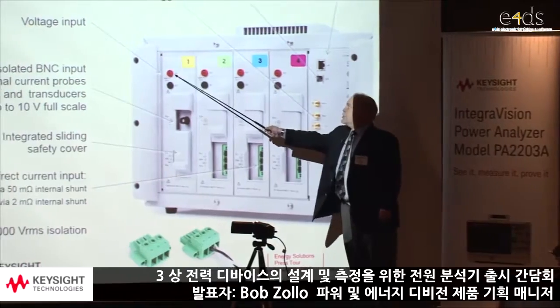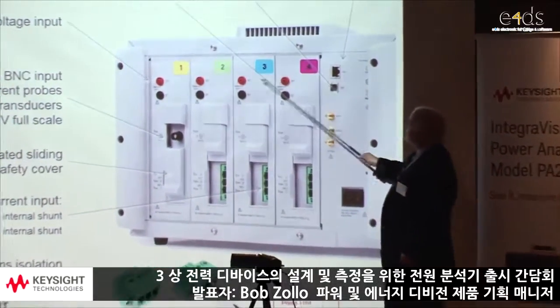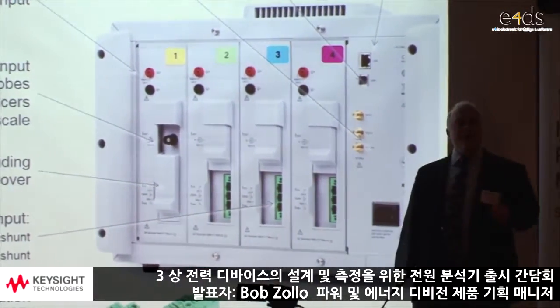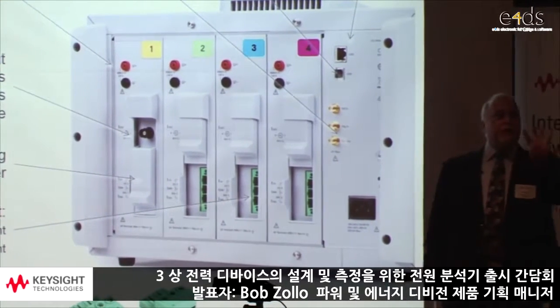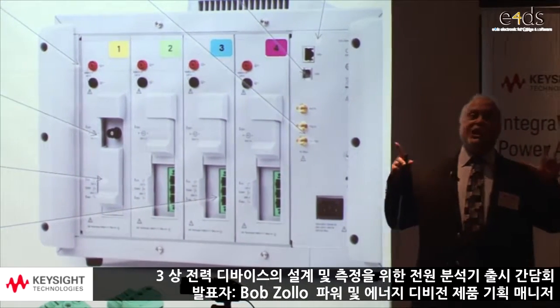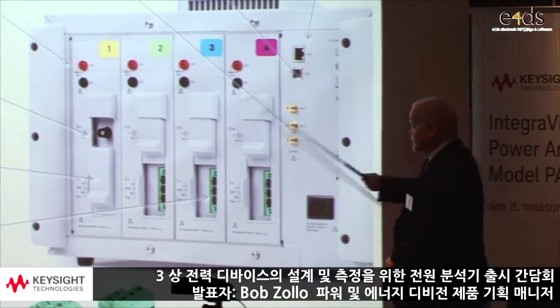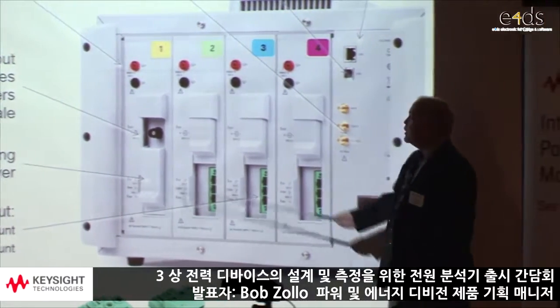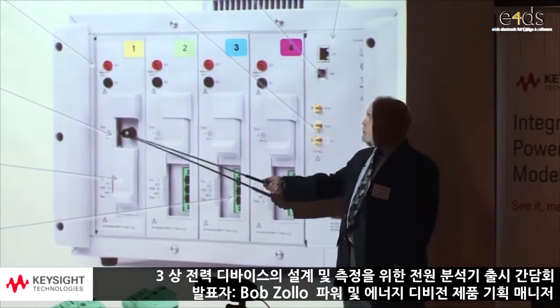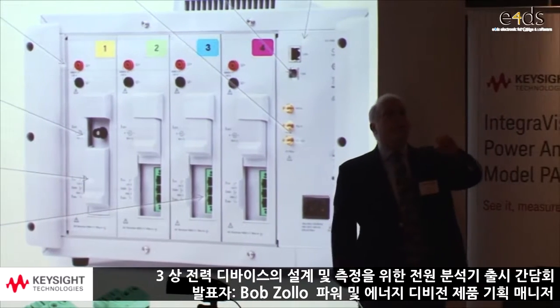I could measure voltage on every channel. That's what these connectors are for, measuring voltage. I can also measure current on every channel. So a 4-channel analyzer is like having an 8-channel oscilloscope, because it gives you voltage and current per channel. This connection right here is for a clamp-on current probe.